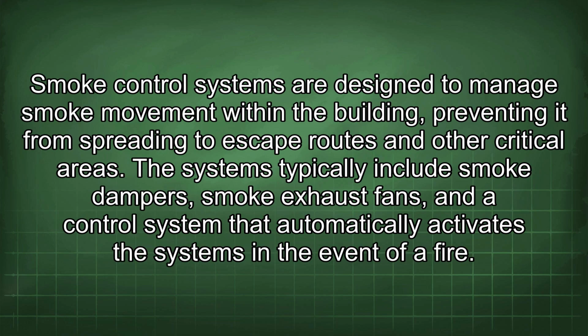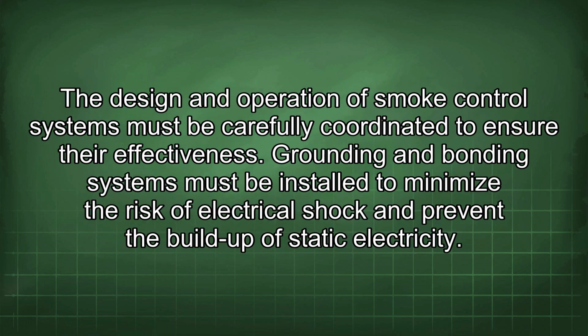Smoke control systems are designed to manage smoke movement within the building, preventing it from spreading to escape routes and other critical areas. The systems typically include smoke dampers, smoke exhaust fans, and a control system that automatically activates the systems in the event of a fire. The design and operation of smoke control systems must be carefully coordinated to ensure their effectiveness.